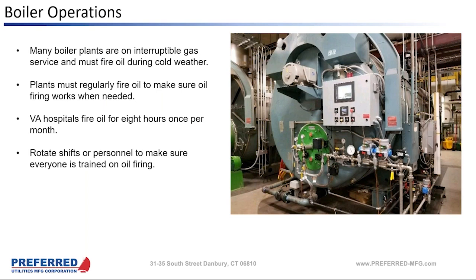So the VA hospitals do a good job of this. They require all their boilers to be run for 8 hours a month on fuel oil. Typically there's 3 in a plant, and the smart plant managers will run fuel in the day shift one month, then swing shift, and then night shift, and make sure all the operators get trained to know how to fire on oil. In fact, the reason I got called out to help get some oil burners lit was somebody had replaced a servo on an oil valve. When you replace the servo, you've got to recommission and re-verify your points. The technician didn't do that because they weren't firing oil. So they tried to switch over to oil, and the system wouldn't run because their oil points hadn't been verified. So I had to go help work them through that.